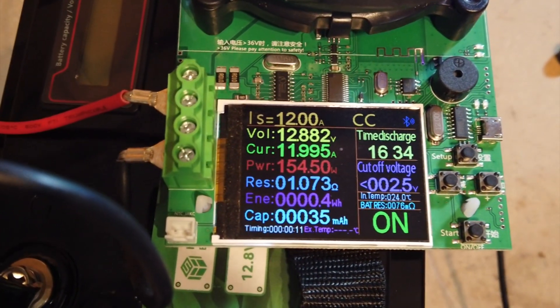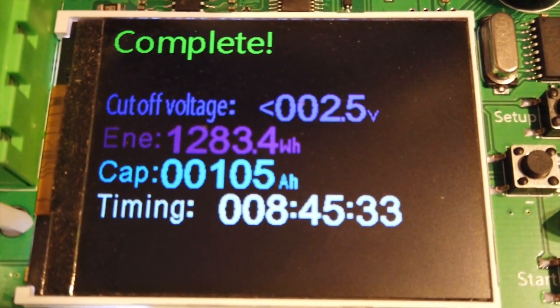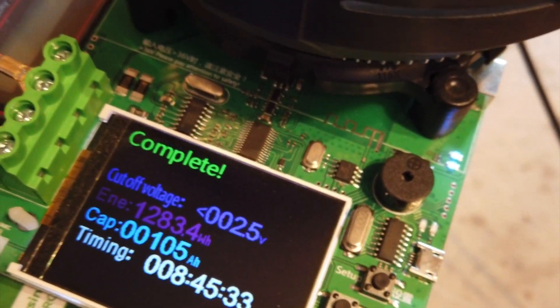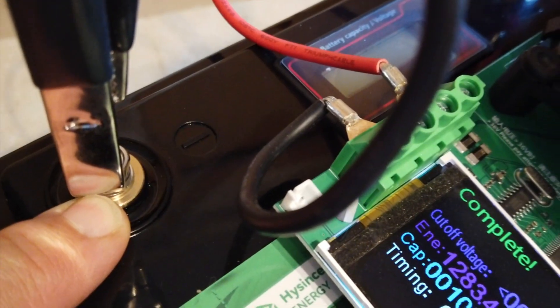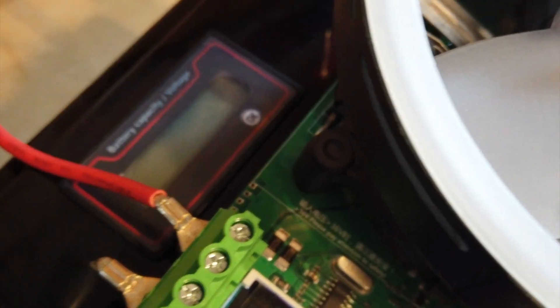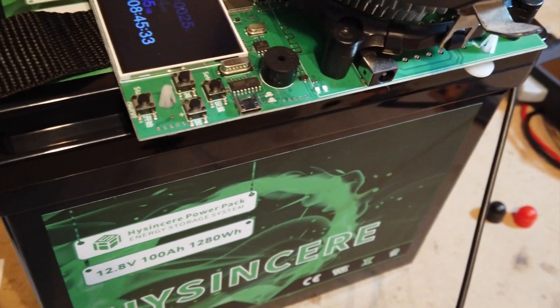We've completed our capacity test on the Hysincere 100 amp hour battery and we got 105 amp hours out of it — it took 8 hours and 45 minutes. So it qualifies, and exceeds, the 100 amp hour rating. I like the smaller profile of the battery if you need that, but I don't like the 6-millimeter bolts — the advertisement says 8-millimeter and they're not. I do like that it has a voltage meter on it, and it's weatherproof.